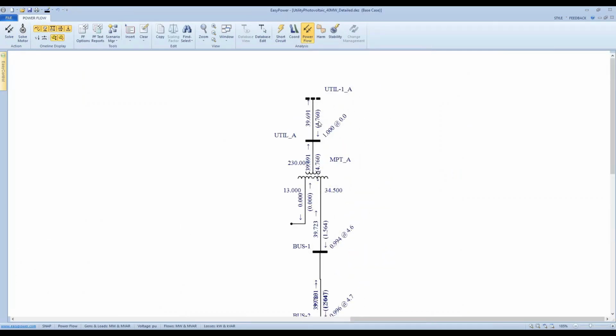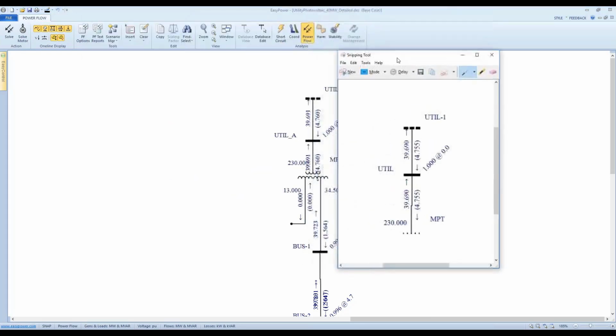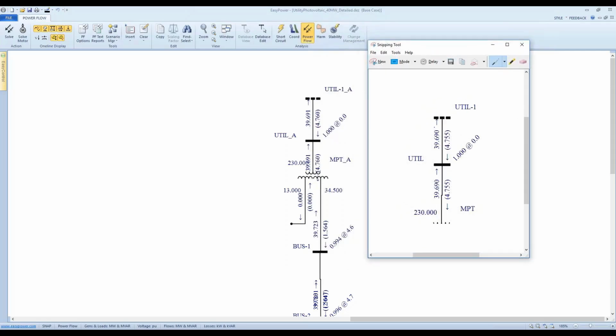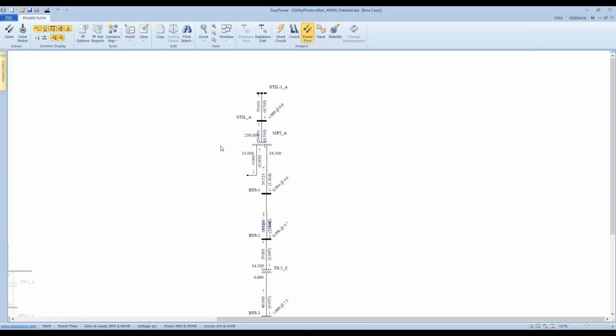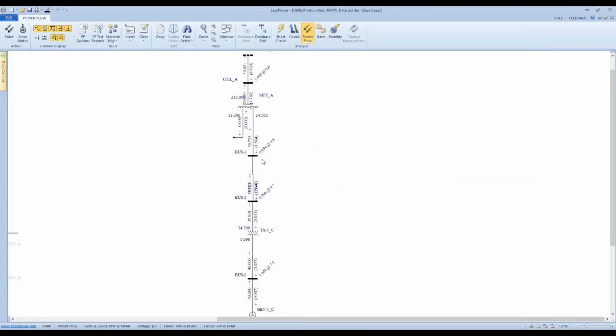What's the active power and the reactive power delivered at the utility bus from my equivalence model? 39.691. If we recall, this is what we got from the detailed one-line design. You can see the active power is just 0.001 megawatt different. The reactive power is just 0.005 megavar different. So I would say it's close enough, right? It's even within 0.1% difference. Now, we understand that because the assumption we made is that the loss across the collector system equivalent and the GSU equivalent is the same. So same generation, same loss, of course you get the same result, right?